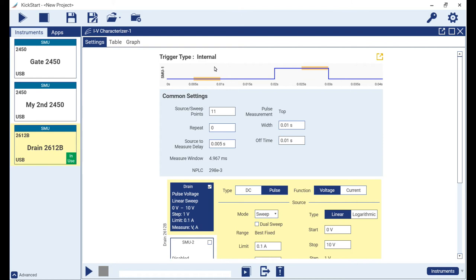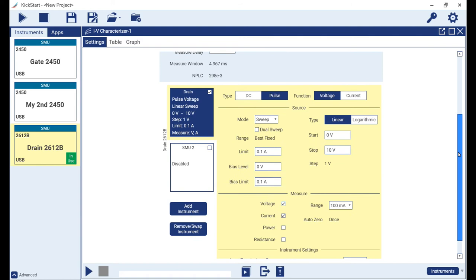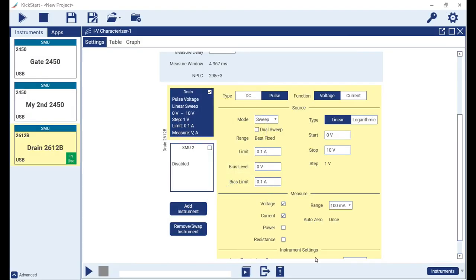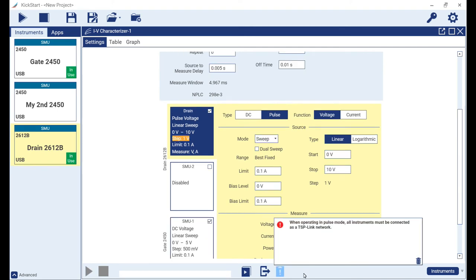Because we want to use the 2450 to test the same device and ensure good trigger synchronization with our drain SMU, we click on the add instrument button, select our gate 2450, then click on the OK button.